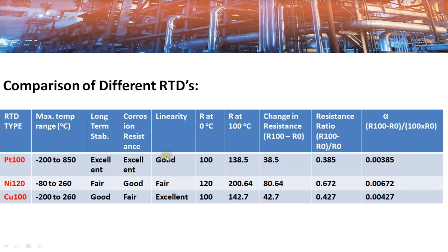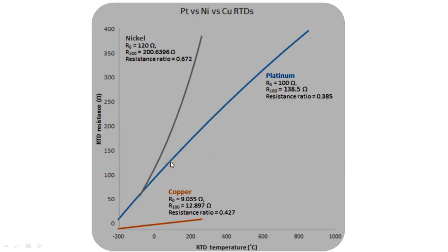If you see linearity, it is best for copper, then platinum, and then nickel. Here you can see the resistance ratios and alpha values for these three RTDs. From the graph, copper RTDs have the best linearity, followed by platinum and then nickel.